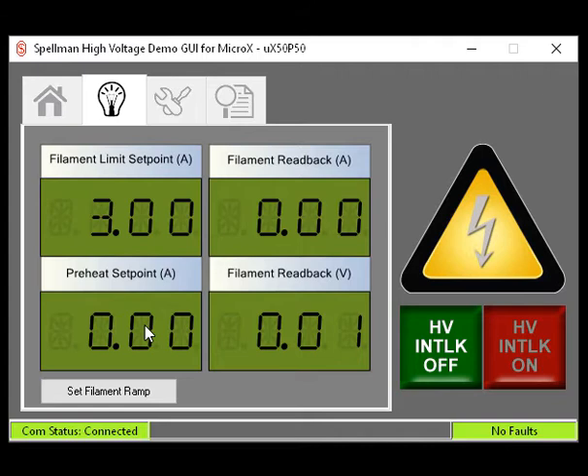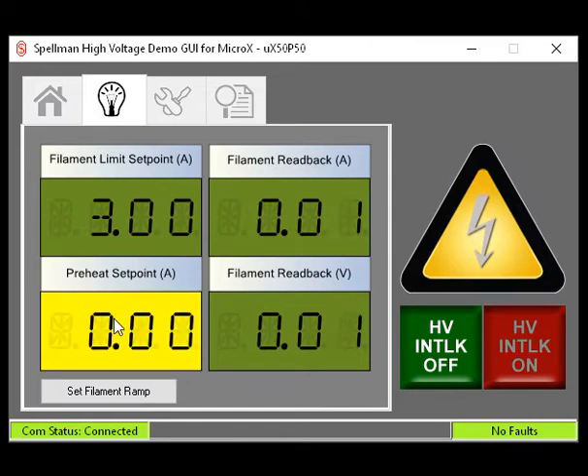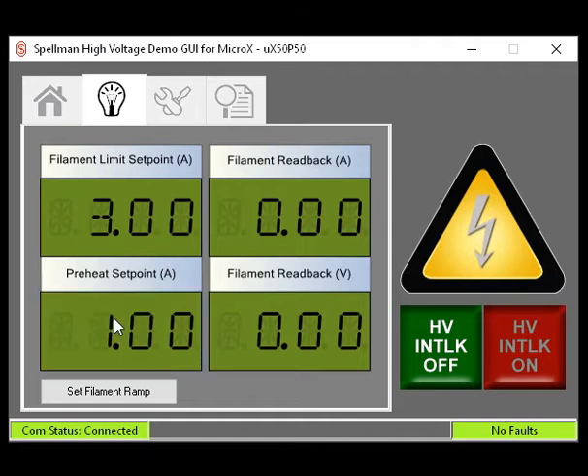It's typically recommended to set this to some small amount of current to keep the filament warm and prevent thermal shock when the high voltage is enabled. Click the box and it will turn yellow. Type in the value and use Enter to exit.